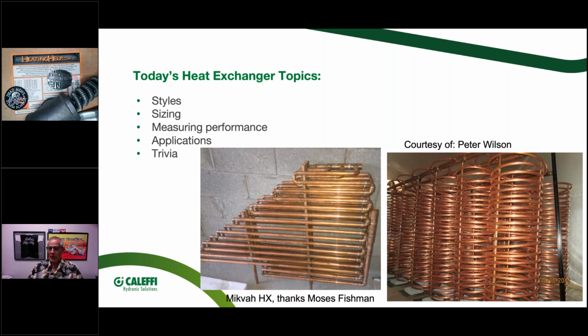And the one on the right, you'll see that commonly with guys who do solar or wood boiler work. They'll make a big open tank out of something—plywood, concrete blocks—put a liner in it, and wrap up a bunch of coils, paralleling the pipes so they can get a lot of flow through them. The key to both of these is obviously copper, one of the best conductors we know, and surface area. It's always a surface area game, whether it's homemade, a plate type, shell and tube, or an indirect tank—it's all about the surface area.